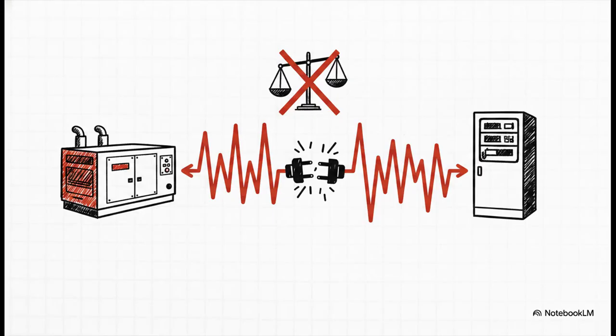Now, when it comes to pairing that UPS with the generator, look, there is this deeply ingrained, completely lazy rule in our industry that says you just size the generator at 1.5 times the UPS capacity. That is a myth probably older than the hospital itself. You cannot use a universal multiplier. You have to rigorously calculate harmonics, step loads, which is the chunk of load hitting the generator all at once, and the massive amount of power required to recharge depleted UPS batteries. If you don't calculate all of this, the generator's voltage is going to swing wildly, and the UPS will just flat out refuse to connect to it.